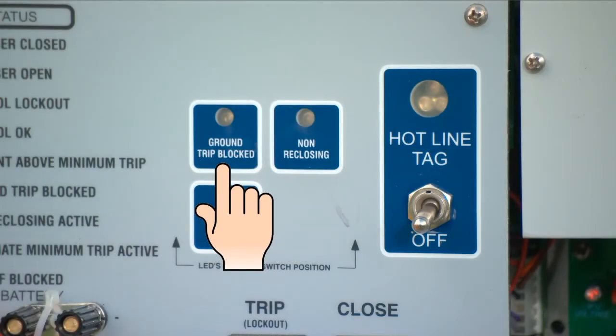Ground Trip Blocked. Ground fault trip operation of the control is disabled when the ground trip block switch is set in the block position. Blocking ground trip operations is useful during known periods of 3-phase load imbalance and is recommended while performing single-phase load imbalance, testing, or switching.